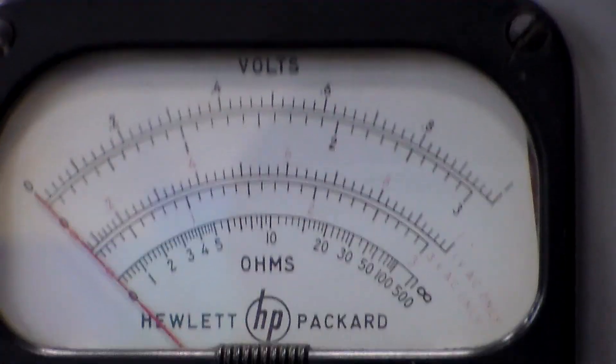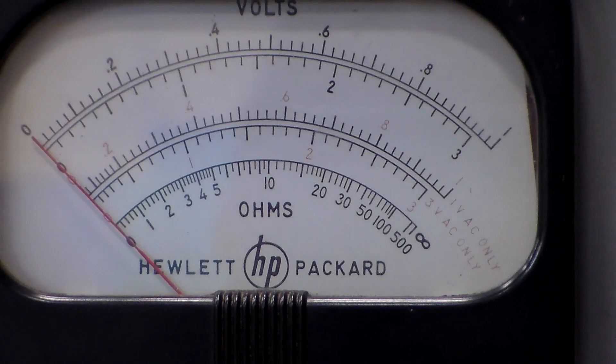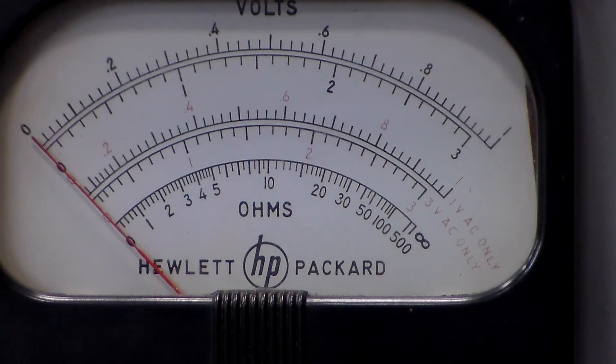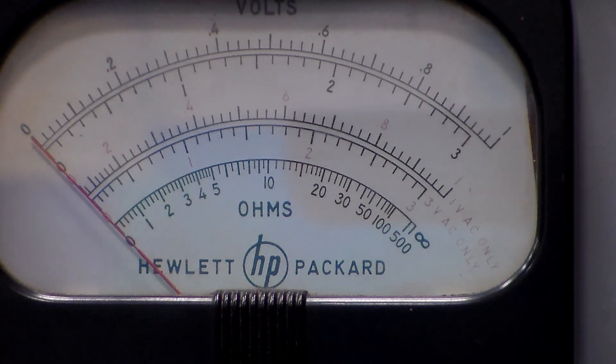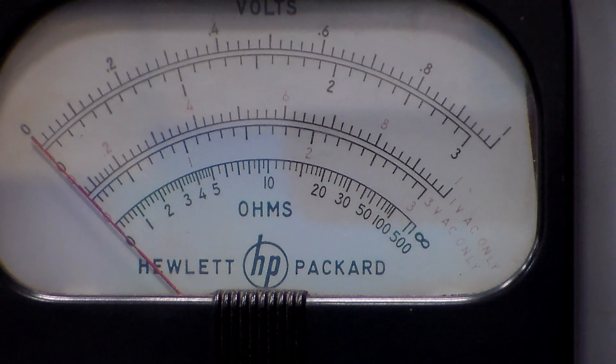It's quite a range that that decade box has and we can verify the performance of the 410B. First up, I'll just zoom in and adjust the camera so we can see the meter. At the moment I actually have it zeroed and we're just about ready to start doing the calibration procedure for the ohms range.